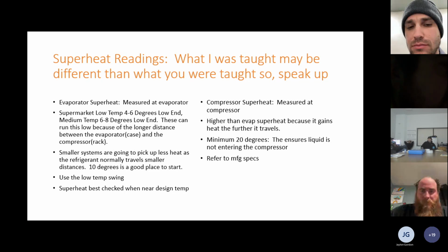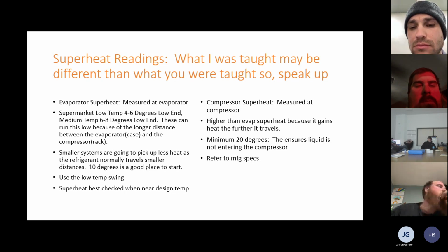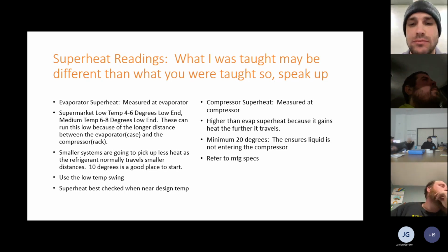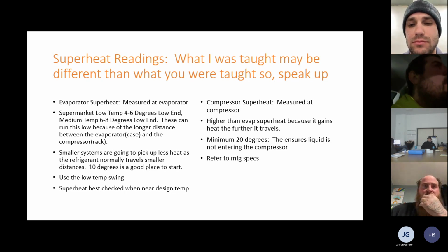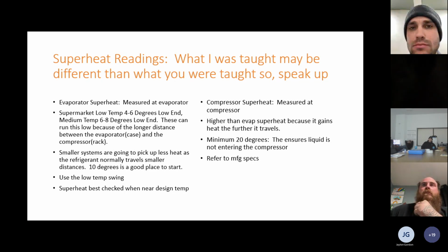What I usually do, instead of opening the door, if I have a walk-in cooler that you want set for 35 degrees, is bring that temperature down on the controller to like 32, and then I'll have a temperature probe in my box, watching it. Okay, it's at 35. What's my superheat doing? My superheat's a little high, so let's open the valve a little bit. Then when I'm done setting it, I'll put the temperature control back to the normal set point and see what it's doing.